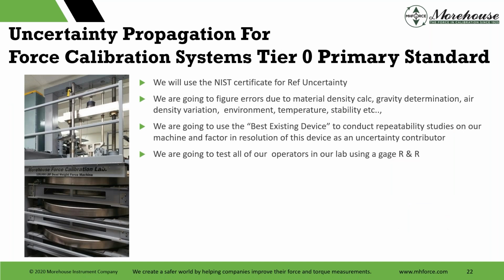So if we're going to do uncertainty analysis, it starts with, okay, so we use NIST. Great. Cool. You use NIST. We have to include their reference uncertainty in anything we do, right? And then we're going to have to figure errors due to the material density, gravity, air density, environmental temperature. And we did have our gravity calculated in the 1990s, and then we had it calculated again in 2022, and it changed by about 0.1 part per million in the facility. So really low change. Was happy that matched out. Probably won't get it done again with that very, very low number.